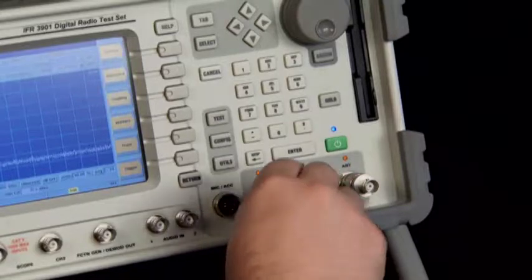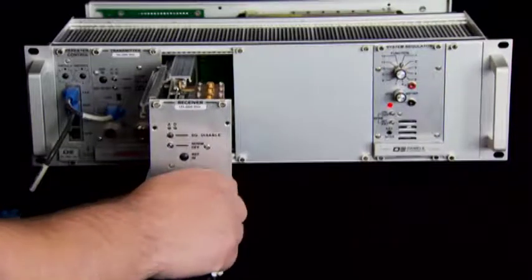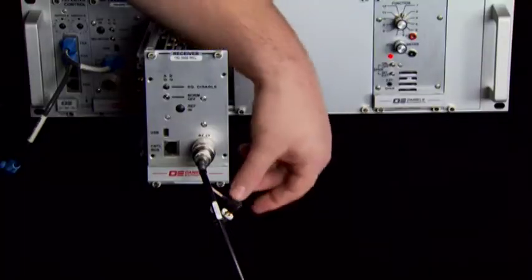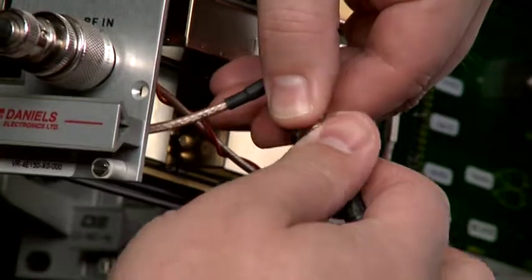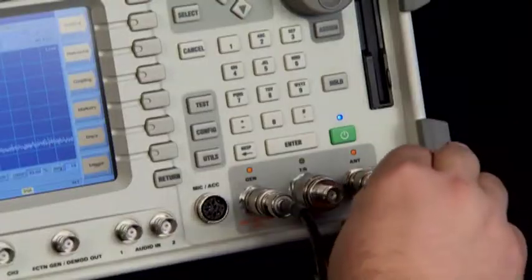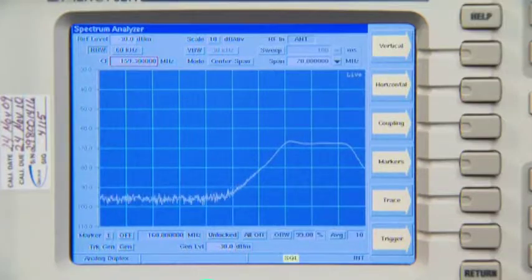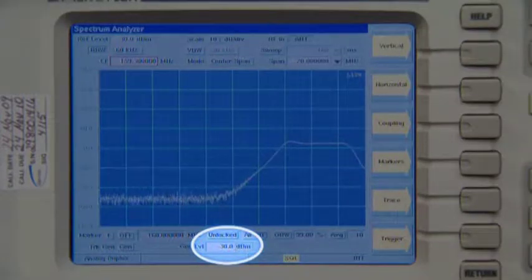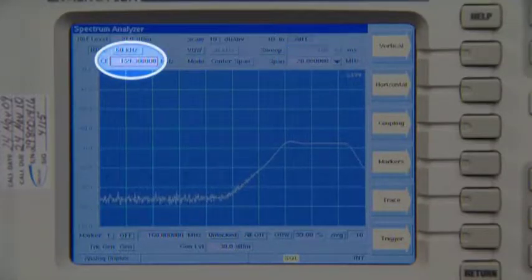Connect the tracking generator output to the RF input of the receiver. Connect the RF preselector output from the adapter to the input port of the spectrum analyzer. Set up the spectrum analyzer as shown, with the tracking generator output at minus 30 dBm, a span of 10 to 20 MHz, and the center frequency at the desired RF frequency.